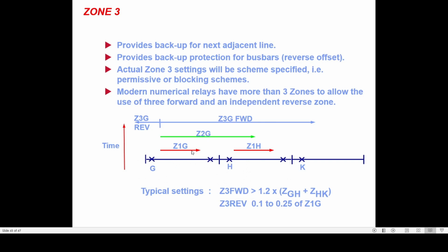So now if you set this relay at G at exactly 260 milliseconds, that means there might be a condition, or there might be a race-around condition in which the relay at G may operate earlier than the operation of breaker failure protection at this substation.